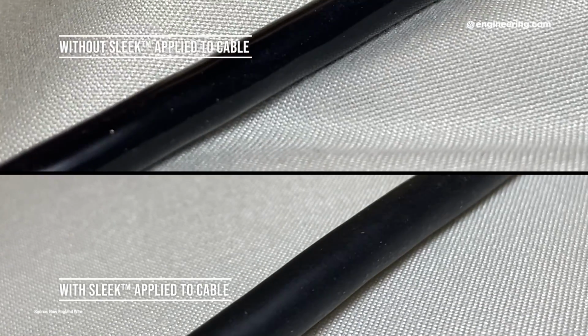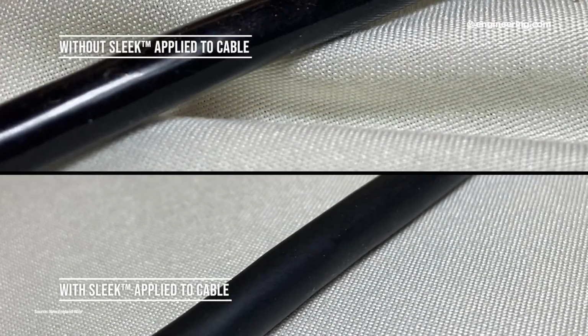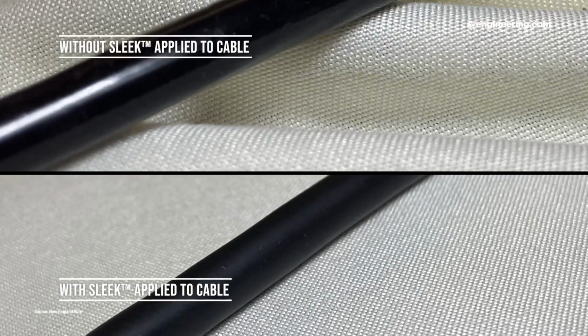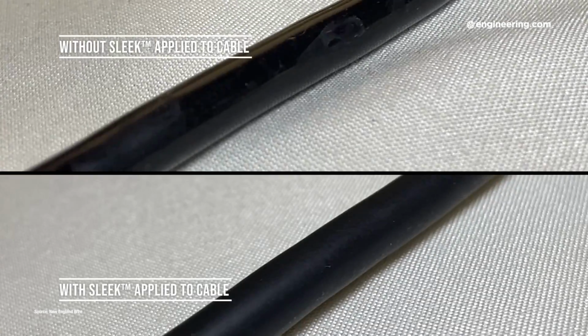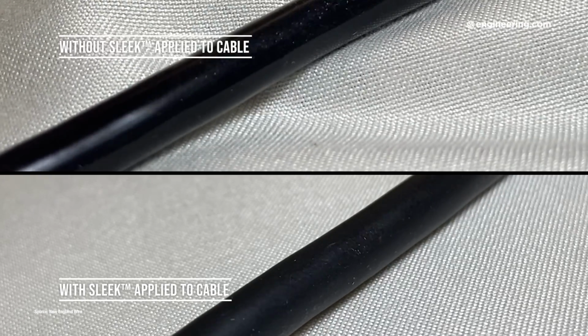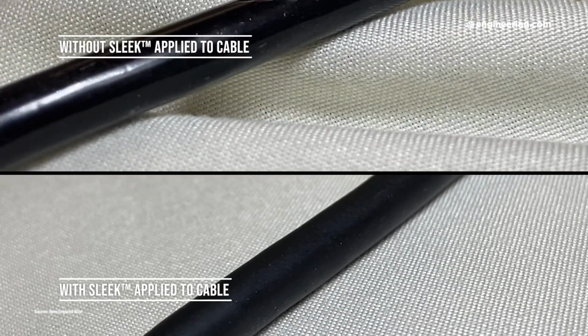But you mentioned tangling of the cable. That's an important thing for medical providers. If a cable gets tangled as they're using it during operation or surgery, it's a big problem. So one of the things we do here is we provide a lubricious coating over silicone rubbers specifically that allows the cable to have a more lubricious feel. Dragging it over surfaces is a lot easier. It has a lower coefficient of friction, so it doesn't tangle as easily as a cable that would be uncoated, for instance.